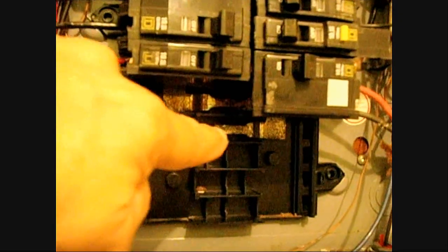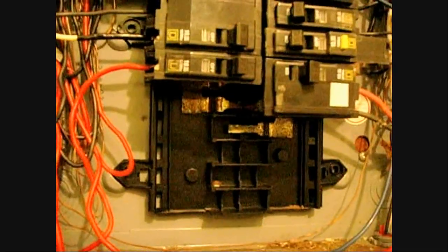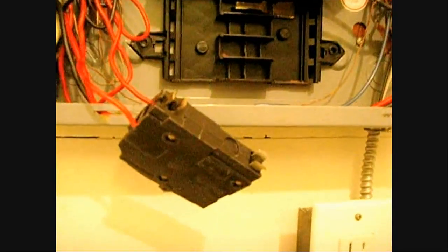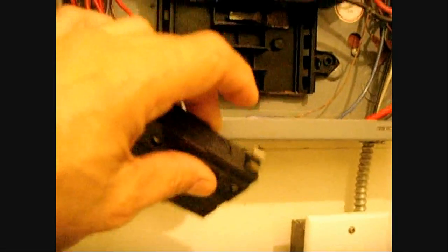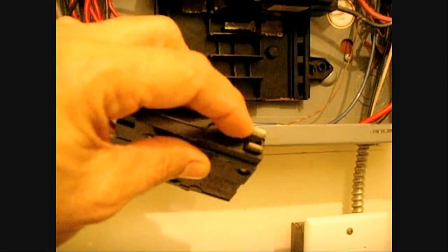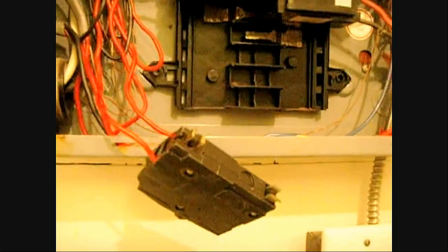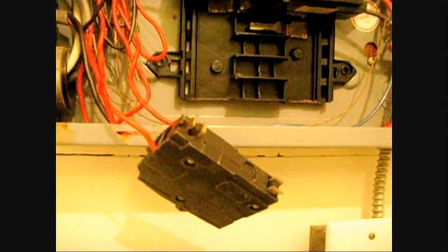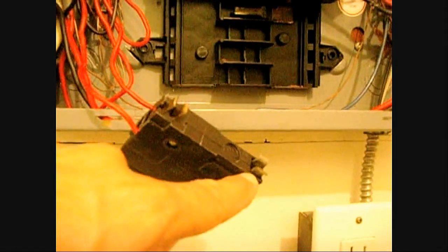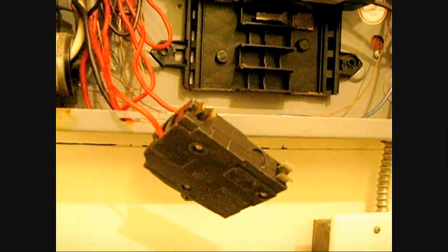Take a small file, a flat file, flatten it out. You're going to want to take a stainless wire brush, go in there and clean that. Once again, make sure the power's off. And then you're also going to want to get the breaker and clean the clip. After cleaning everything, I like to put a compound called No-Alox. It prevents aluminum oxidation. It works extremely well between aluminum and aluminum connections and aluminum and copper connections.